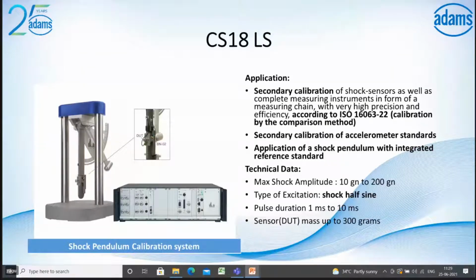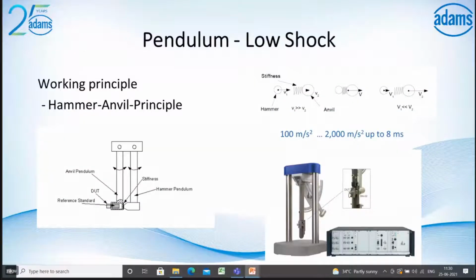And CS18LS, that's a low shock calibration system for shock sensors according to the ISO standards by comparison method. In this method, you will have a hammer and anvil, so a hammer pendulum and an anvil pendulum. On the anvil pendulum, you will mount the reference standard accelerometer and the DUT. The maximum shock range is 200 G, the type of excitation is half sine, and the maximum pulse duration is 10 milliseconds. This is how the hammer-anvil principle works to generate the shocks: the hammer hits the anvil pendulum and generates the shock.